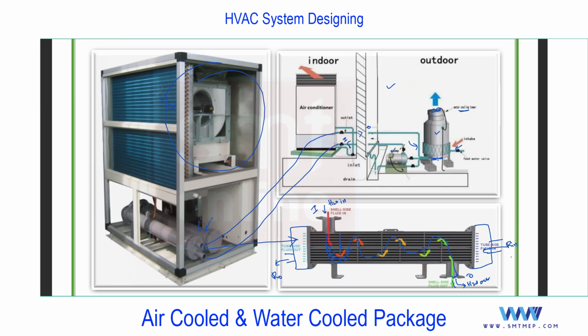Since in this system the condenser uses water to cool the refrigerant, we can call this a water cooled system, and this system is a package. So it's a water cooled package. And remember, this unit we can place inside the building, but this cooling tower we cannot place inside the building because it is used to separate the hot vapor from the water. So this must be placed outside the building only. Got the idea? At this level, just remember, the cooling tower is used to cool the water.